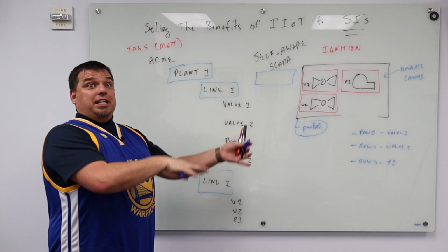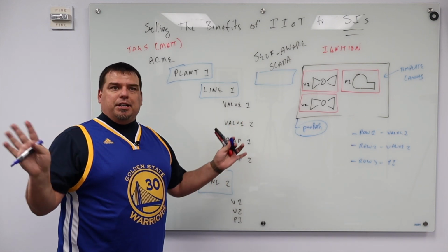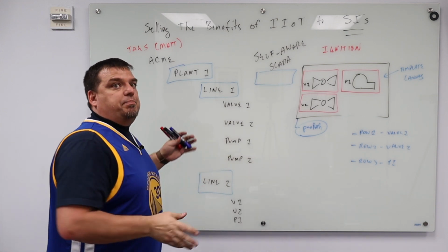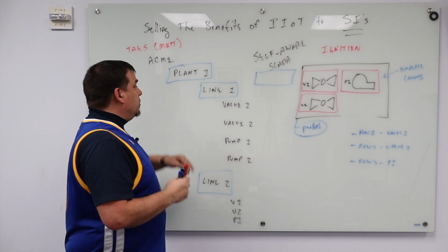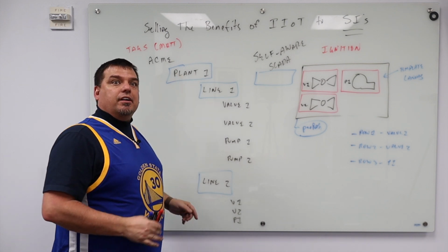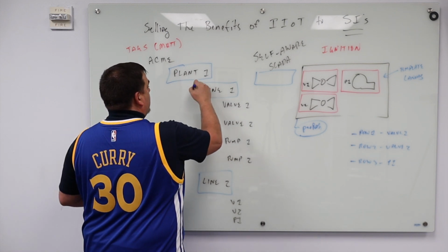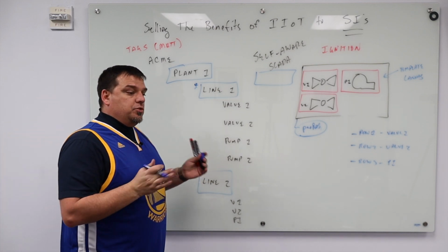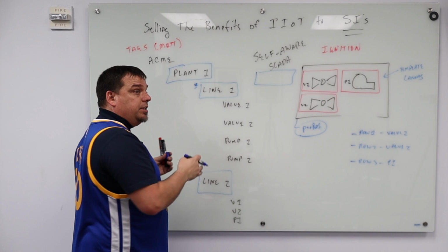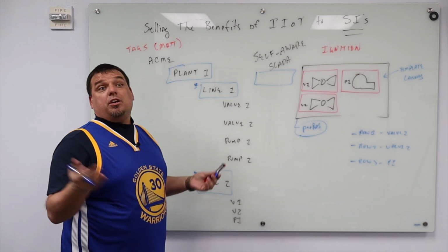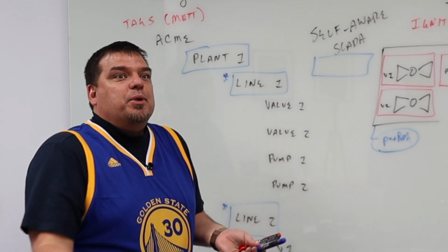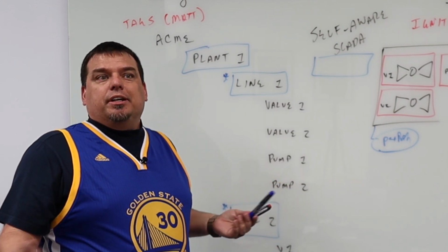Now, you want to know the advantage of Ignition 8? And again, if anybody doesn't know anything about Ignition, I apologize, but the big advantage of Ignition 8 is that you will no longer have to recursively browse here. You'll be able to subscribe to this. Yes. So the new tag structure allows you to not only subscribe to individual tags, but also the properties of those tags. Yes. So you will no longer need to browse to see what exists there. You can subscribe to it.